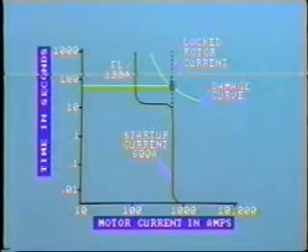From our earlier curve, we see that the motor takes about 10 seconds to start. However, if the motor fails to start, this high value of current would remain on for a longer period. The allowable period of time is shown by the bottom end of the thermal limit curve, in this case, 50 seconds. The instantaneous overcurrent relay is set too high to provide protection.